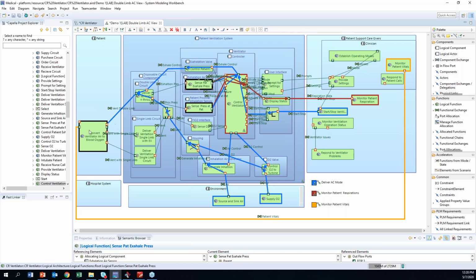But having a model of the patient is really important, because that allows you to develop test cases for the system that you would want to validate when you actually have physical hardware. So you start with a model to generate the data and create the test cases, and then you use the real hardware at some point to validate the test cases.